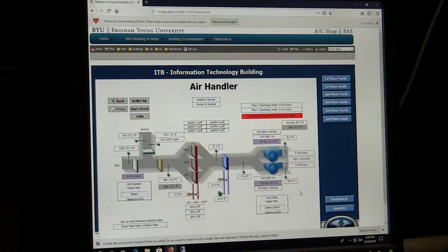We're going to spend a little time talking about an air handler, some of the temperature sensors, and how we can use analytics to first see if everything's working right, and then use other tools to calibrate those, making sure the system has the correct temperatures all the way through, from return and outside air, through mixed air, to discharge air, so the system sequences correctly and we don't waste energy thinking we're at 55 degrees when really we're at 50 or 52.